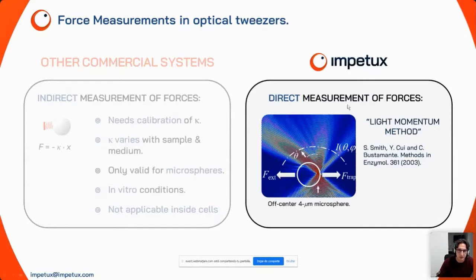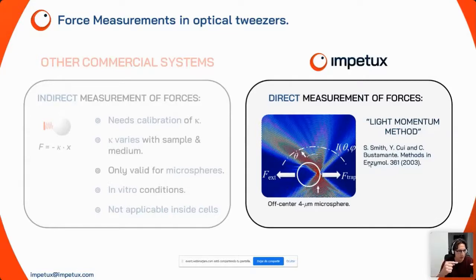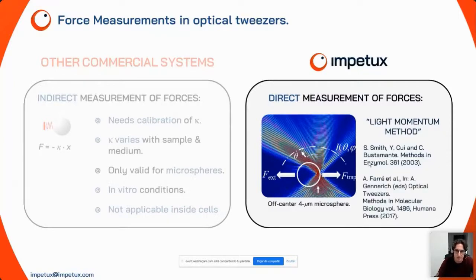If you can look at the transmitted light pattern and measure the momentum changes, you have a direct route to force. This method was initially proposed by Steven Smith and Carlos Bustamante from Berkeley, using a two-laser counter-propagating configuration. Our contribution has been to demonstrate that this momentum method can be applied to a single-laser optical trapping system, and this is what we have patented and protected.